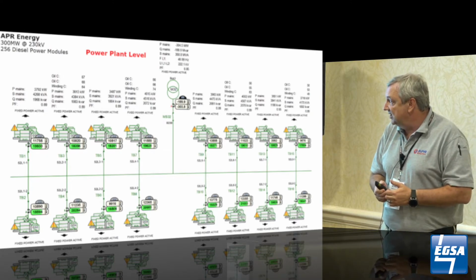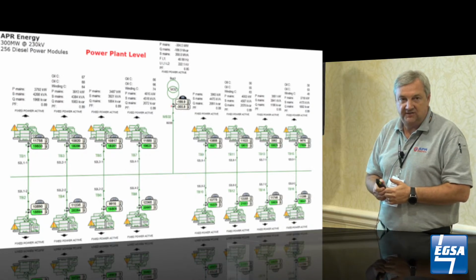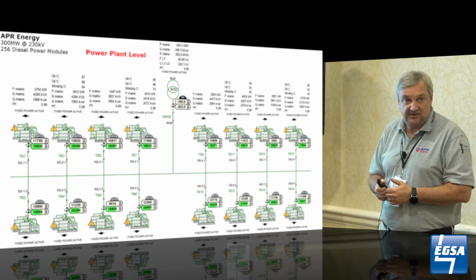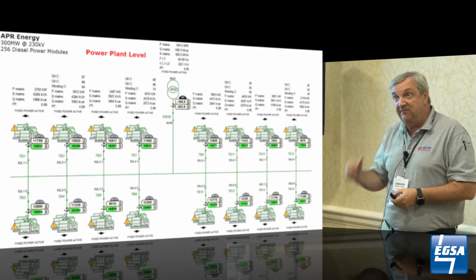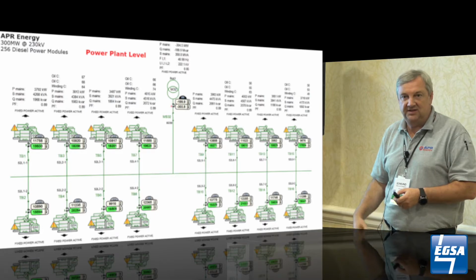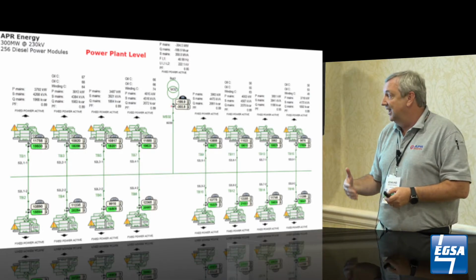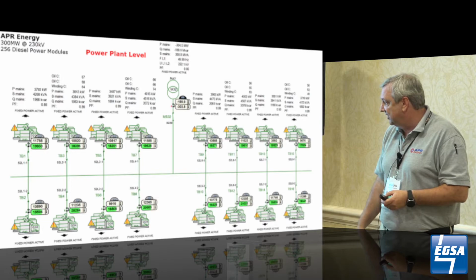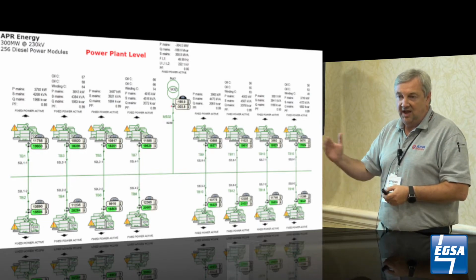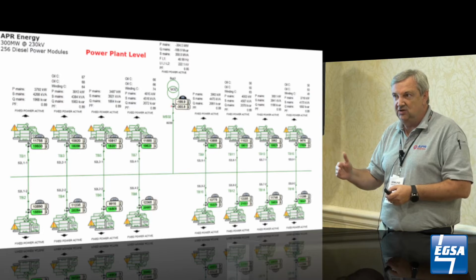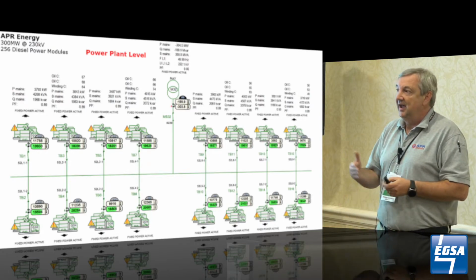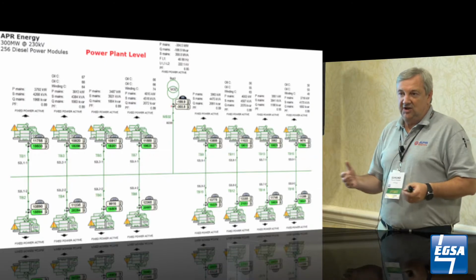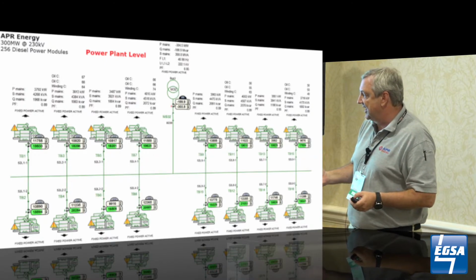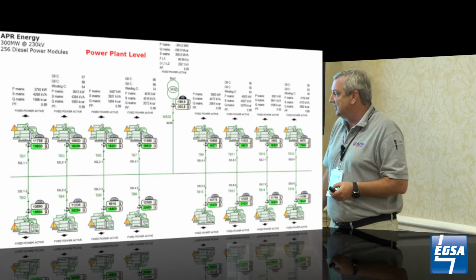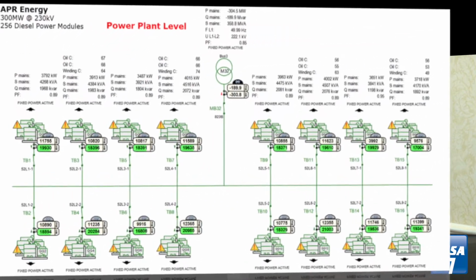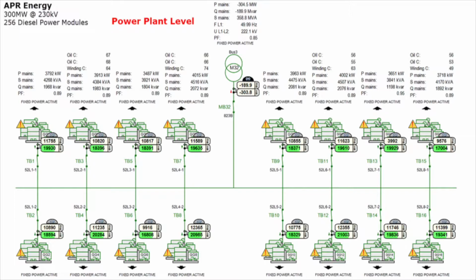To achieve that, we didn't want to be pushing the capability curves on our generators, so we installed capacitor banks. I've got two 50 MVAR, 230 kV capacitor banks helping to do power factor correction. What that's helping me with is, when the power plant's up at full capacity, and if the customer does ask for that, I'm now somewhere about a 0.82, 0.83 power factor on my generators, and I'm not stressing the electrical system. If the customer hasn't asked me for power factor and we're running the site at, let's say, 0.95 power factor, the generators are all running at unity because they don't have to make any VARs. It's all being done by the capacitor banks.